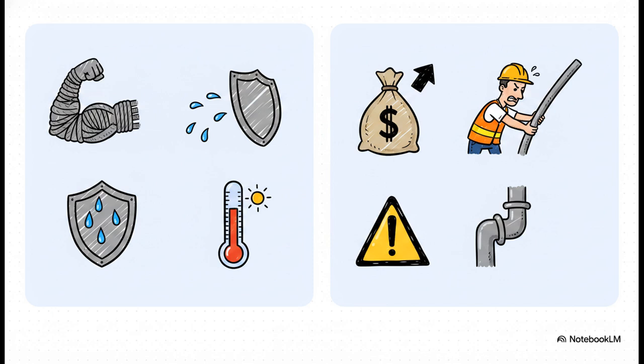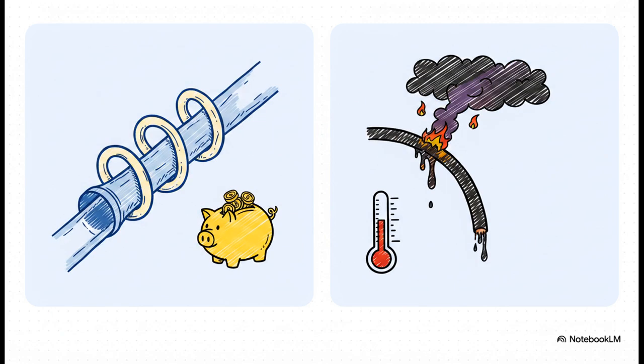And also, because of that 3D cross-linked structure we talked about earlier, its increased rigidity makes routing these cables through tight spaces or complex panel layouts an absolute nightmare for installers. Now, here comes the classic "it depends" moment with PVC. Because despite XLPE's clearly superior stats, PVC remains incredibly popular. Why? Well, it's cost-effective and it's highly flexible, which is perfect for snaking through tight conduits. Interestingly, thanks to the chlorine and its chemical structure, it is inherently flame retardant.